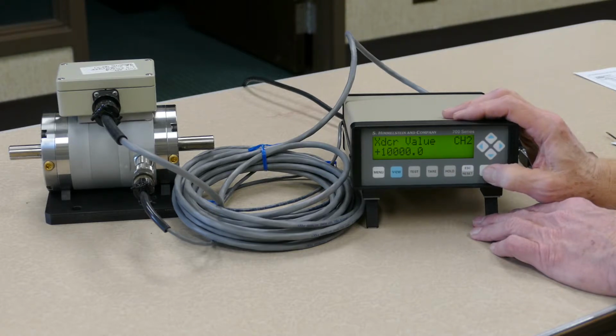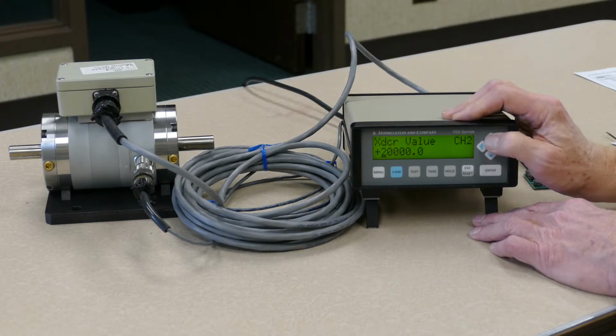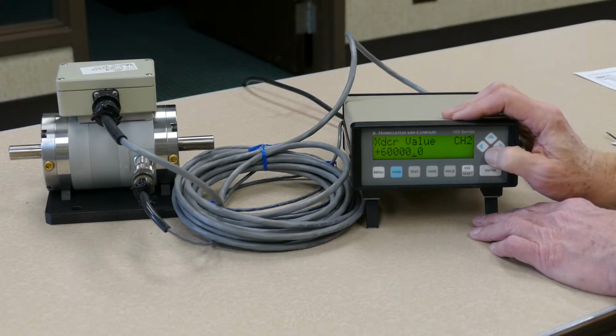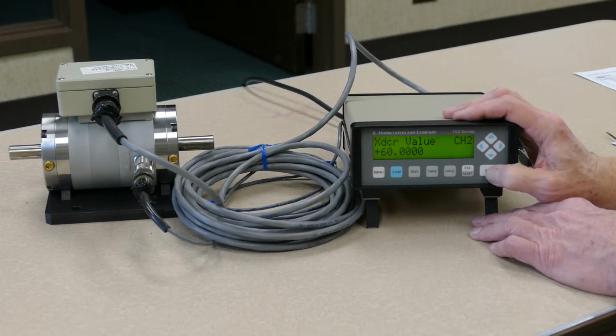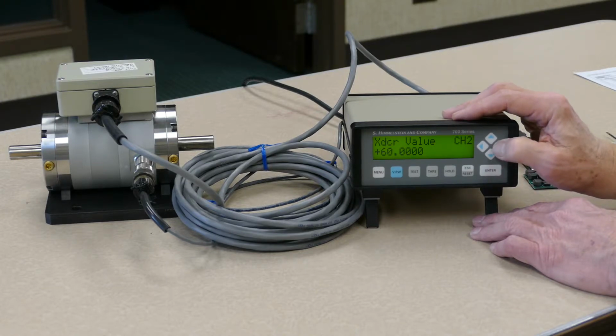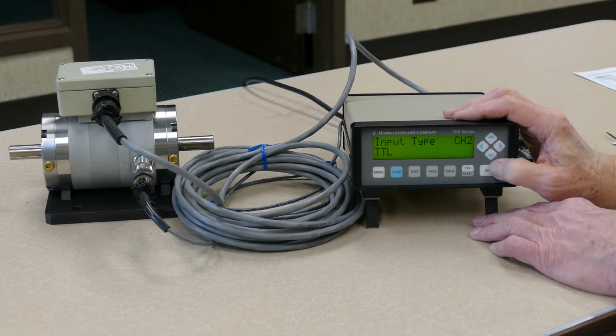And now it asks for the transducer value. So we want this value to also be 60 with a 60-tooth gear as the input. So we hit enter. Change the first digit to be 60. Move the cursor to the decimal point, and with the down arrow, move the decimal point to the left. Hit the enter key again to accept that value, and then hit the right arrow again.